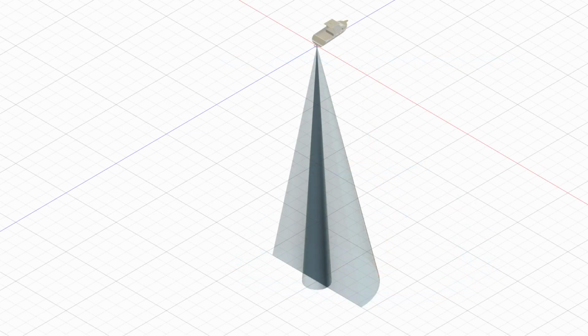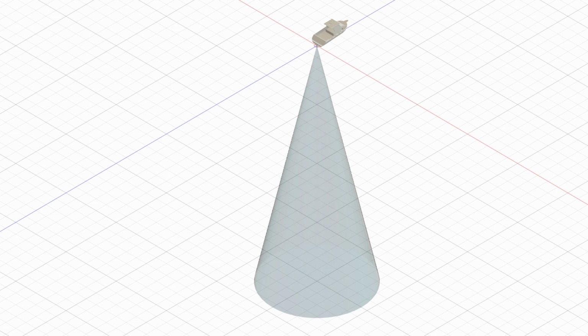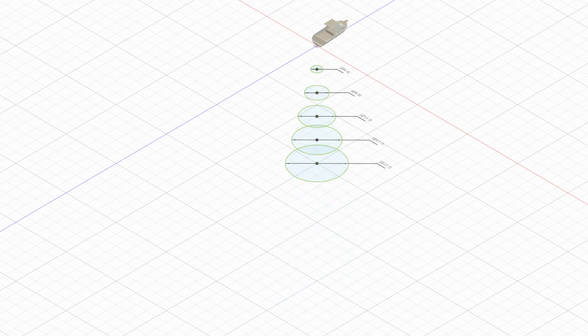This slide shows the difference in detection volume between a 6-degree cone in the centre and the 25-degree cone on the outside. In this slide I've cut the outside cone in half to make it easier to see the inner cone. I'm going to go through the same exercise we just did for the 6-degree cone with this 25-degree cone, showing how the rings expand as the beam goes deeper. Since we've already done it once with the 6-degree cone, I'll let this play through at a faster speed.